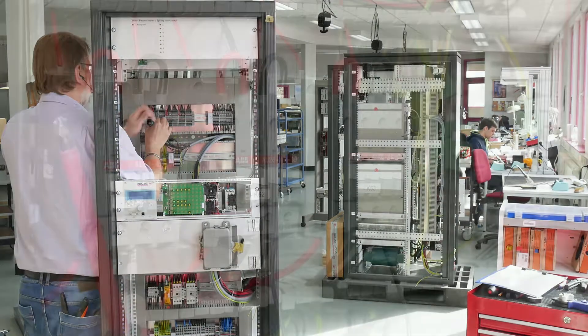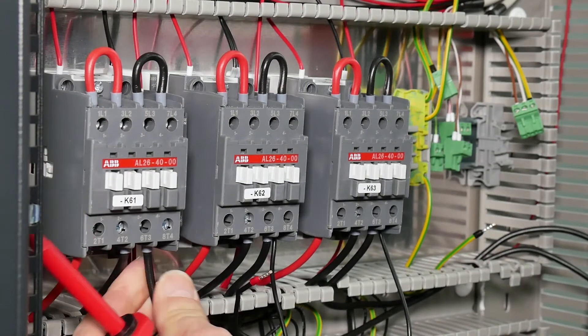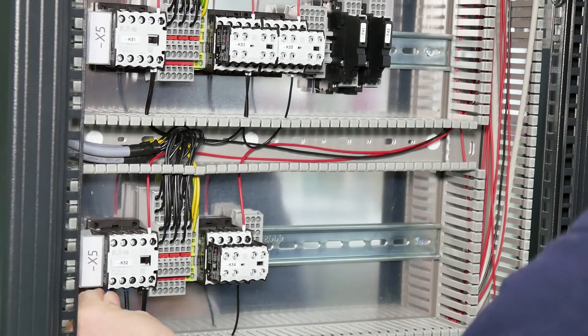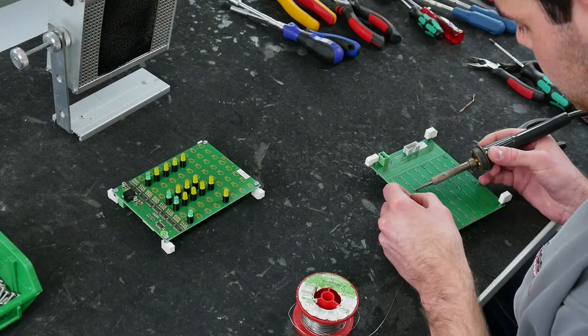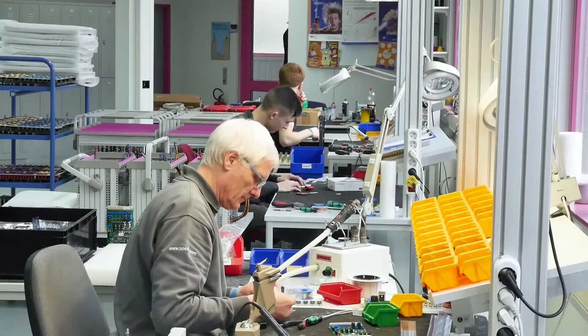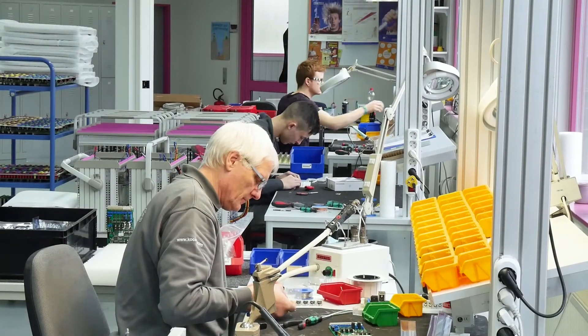The C systems are designed for circuit breaker testing, while our CF systems can be used for drive tests on disconnectors and earthing switches. For maximum testing functionality, both devices can also be combined in a CCF system, designed for testing the whole Switchgear.